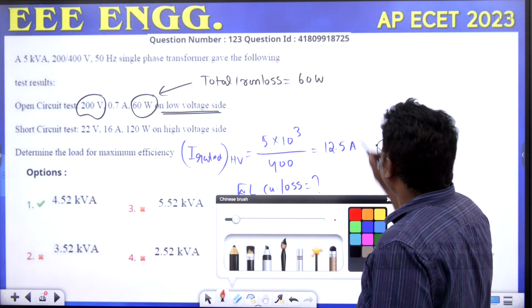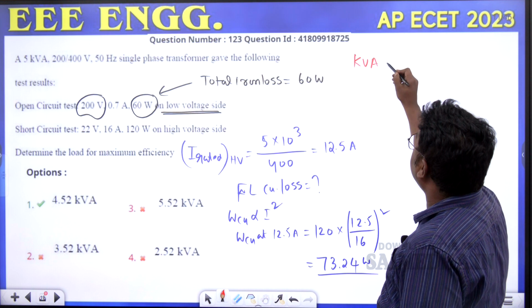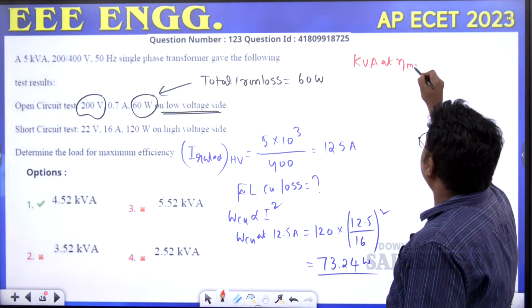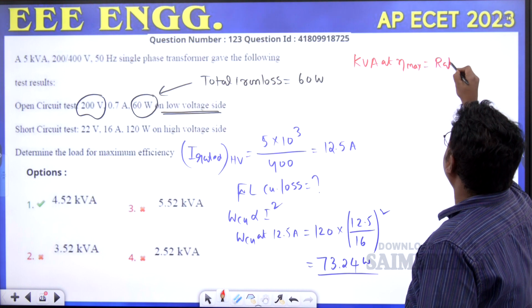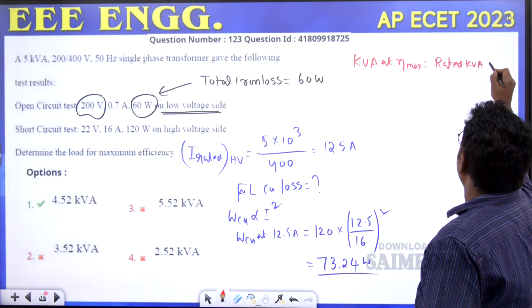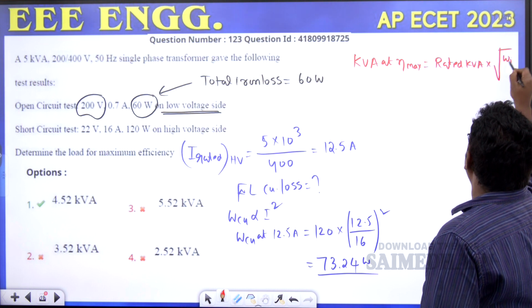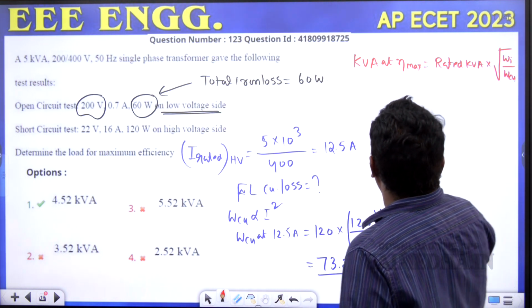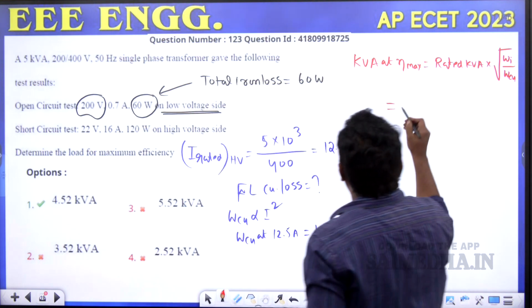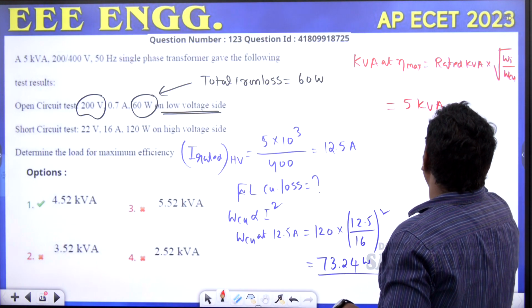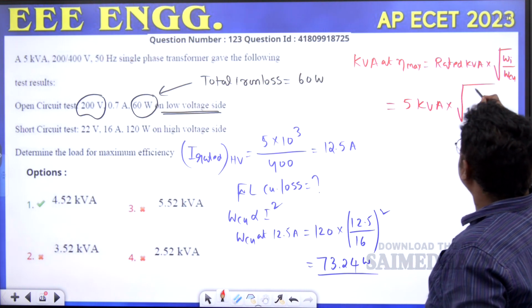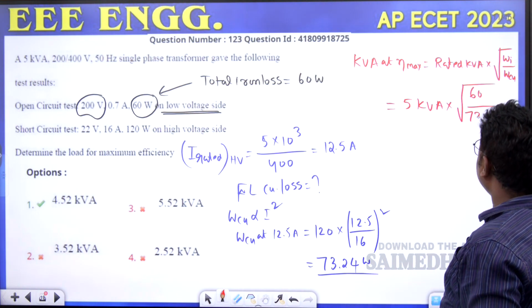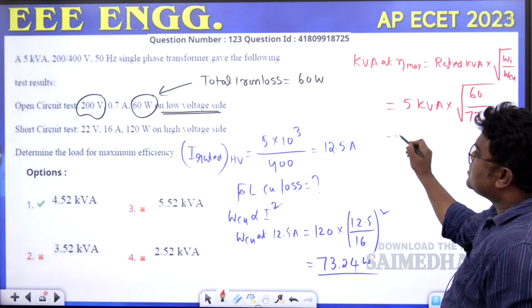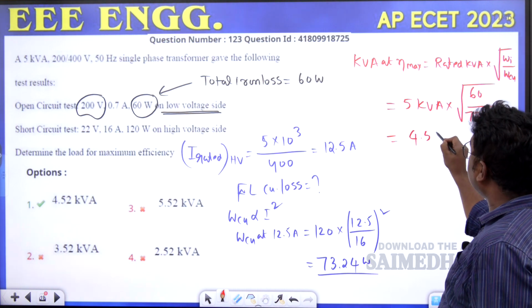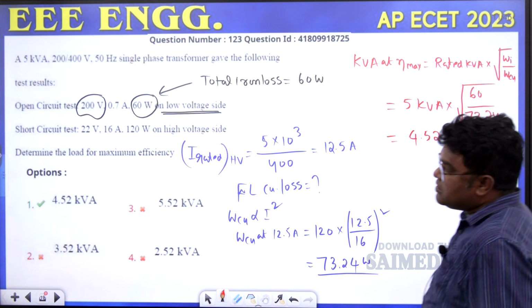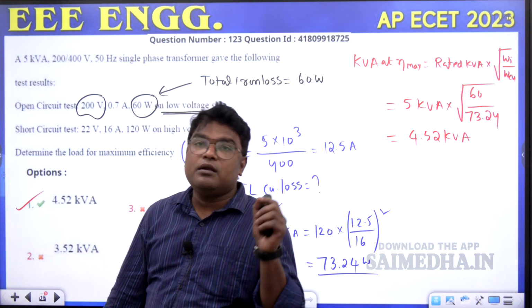How do we get the KVA rating? At maximum efficiency condition, the KVA is equal to rated KVA multiplied by the square root of iron losses divided by full load copper losses. Rated KVA is 5 KVA, multiplied by iron losses, 60 watts, divided by 73.24 watts. By solving this we can get 4.52 KVA. So the answer for this question, option 1, is correct.